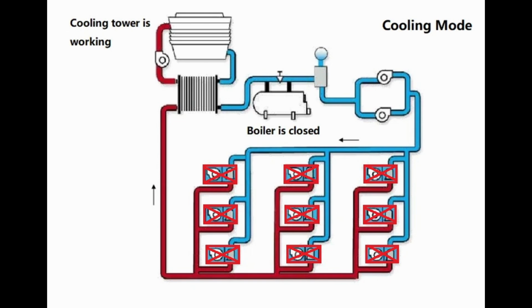Put the pumps in hand during the swap. Don't forget you may have separate pumps for the building loop and the tower loop if you are working on a closed loop system. The tower loop pump is sometimes referred to as the spray pump.